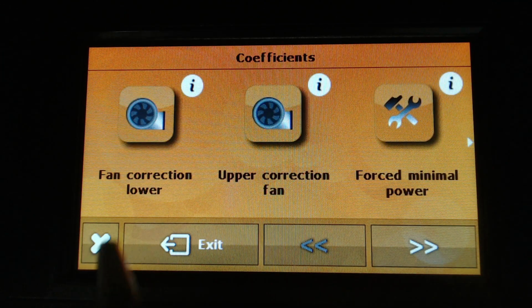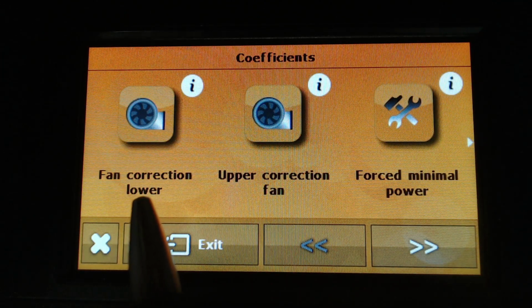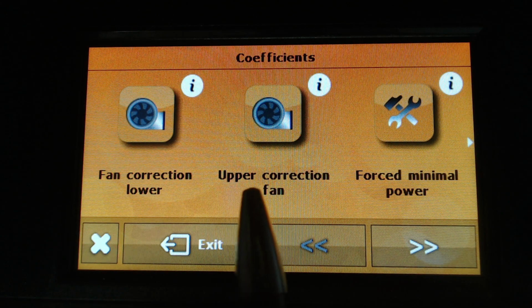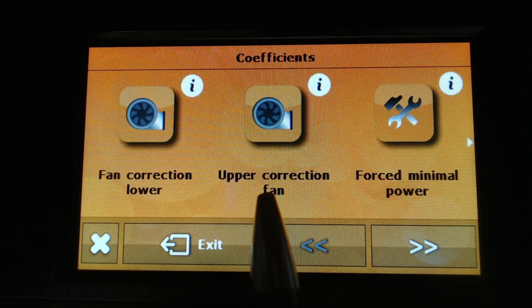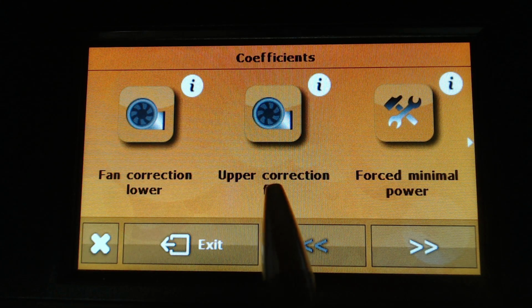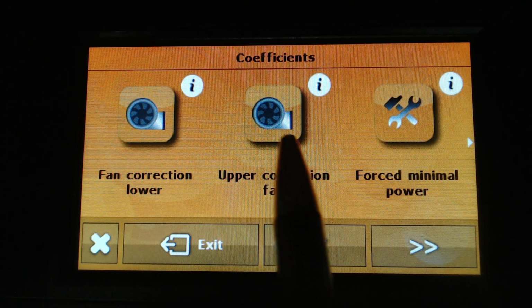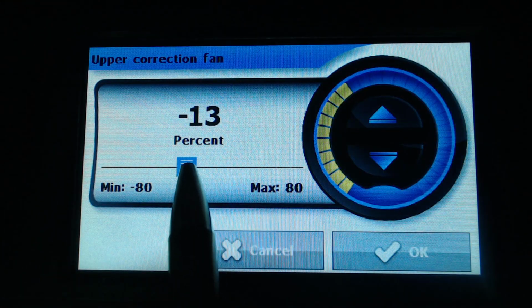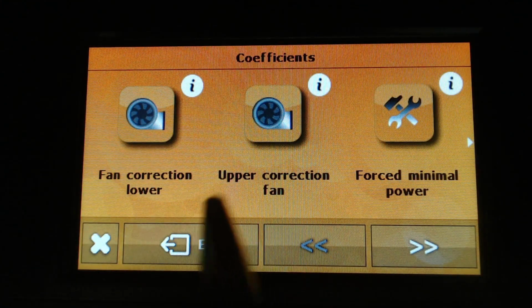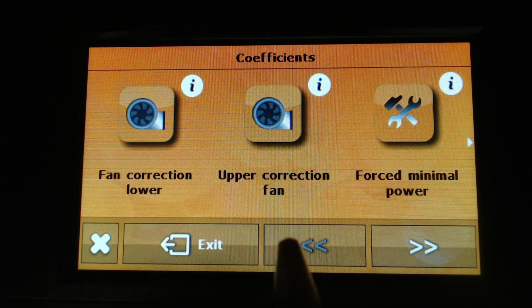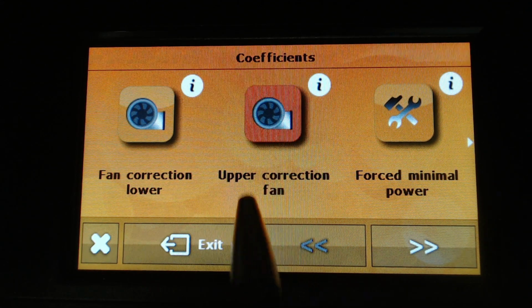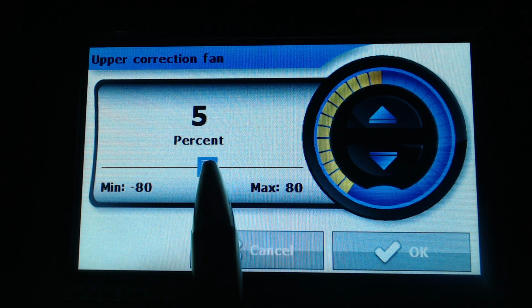So in coefficients you have fan correction lower, which is the function for minimal speed, for minimal power correction of the fan, and here upper correction fan is for maximal power. So when we wait for the boiler to reach maximal power, and for example we see that the flame itself is too short, too bright, too aggressive, we can decrease the maximum speed of the fan to make sure that the flame is not too aggressive.